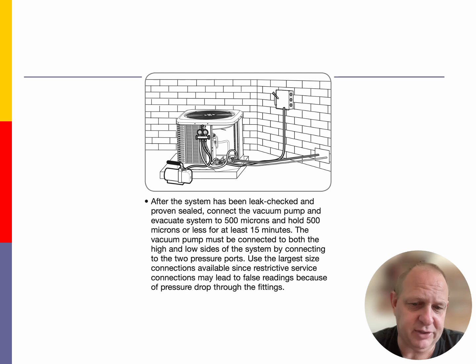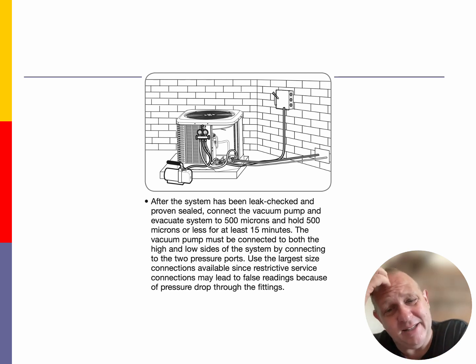It might take us longer to pull those vacuums down, but a clean system, man, so fast to pull those vacuums. After we get done vacuuming it down to the proper level, we're going to do a vacuum decay on this. We're going to hold it for 15 minutes. We're going to watch that vacuum, and that vacuum should not increase more than 100 microns over a period of 10 to 15 minutes. And you're really going to watch this because this is going to indicate whether you have a small leak on the system.